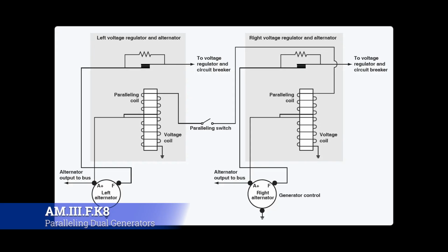Paralleling a dual generator electrical load system involves connecting those two generators so they can operate together to supply power to the electrical bus or the load, wherever it's going, while still ensuring the load's effectivity and maintaining stability - meaning it supplies enough power and gets everything going where it needs to go.